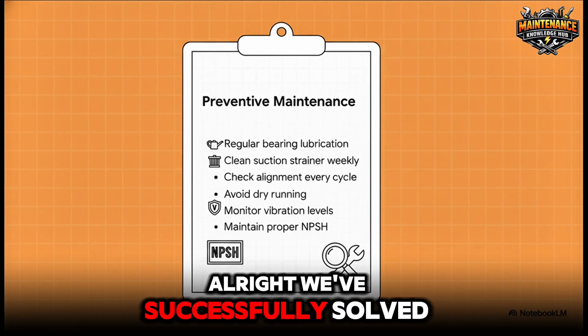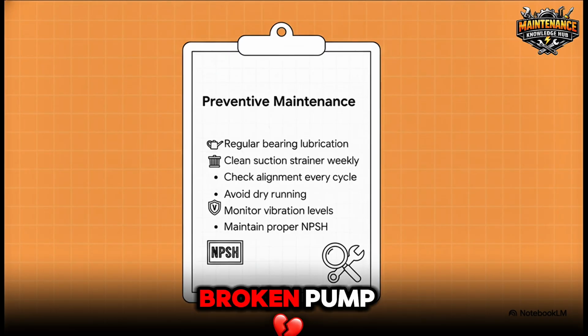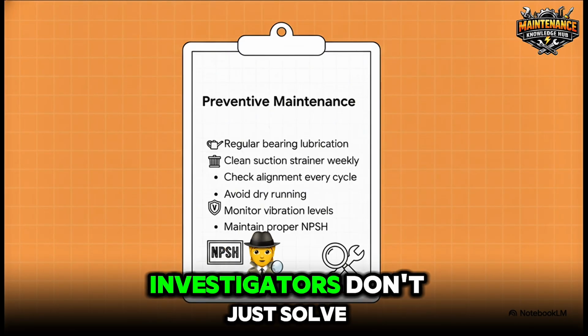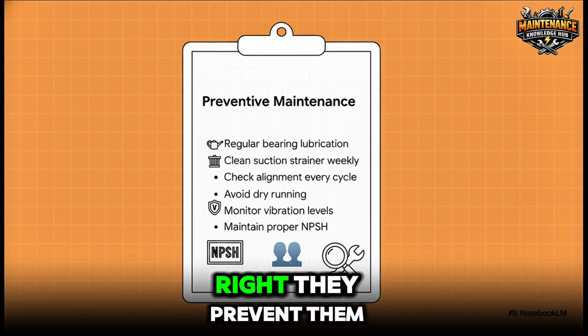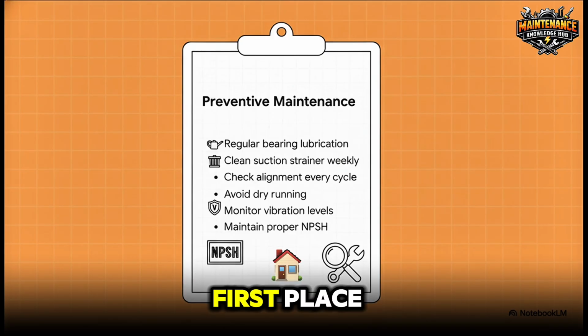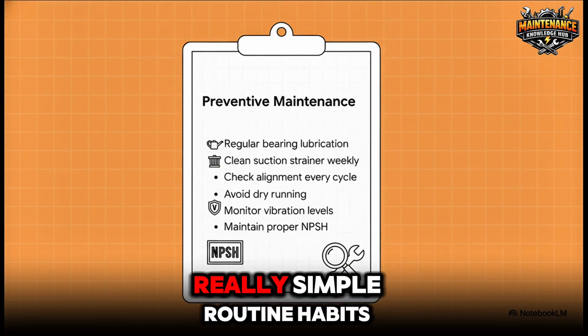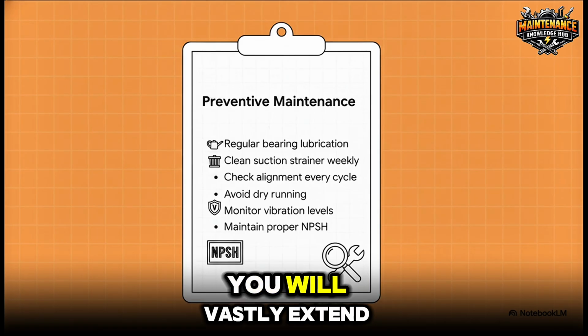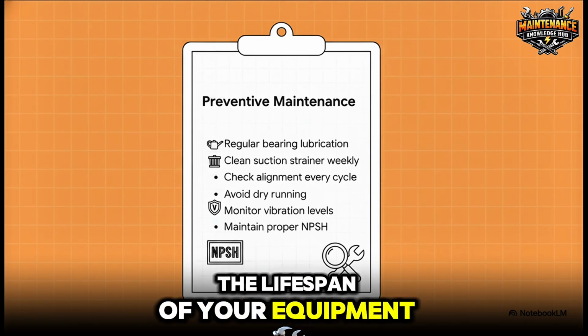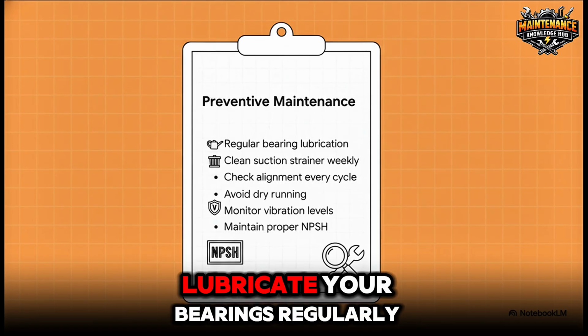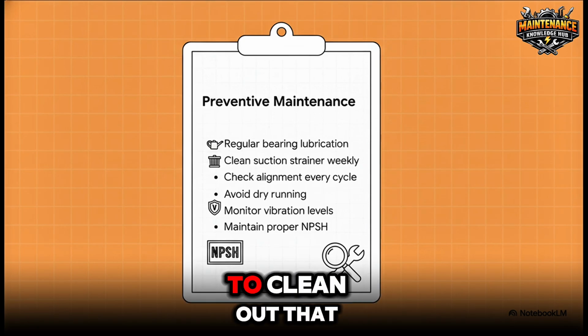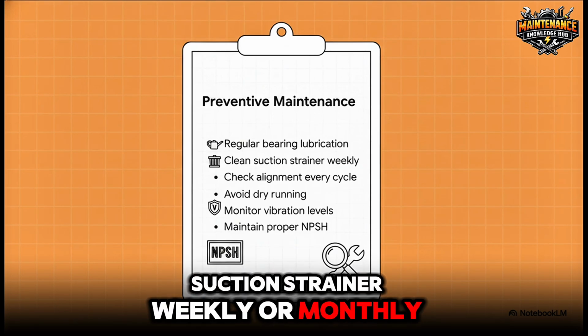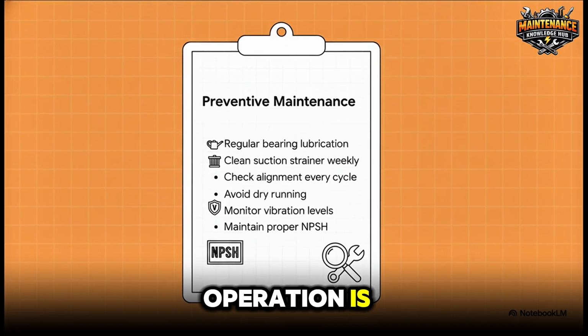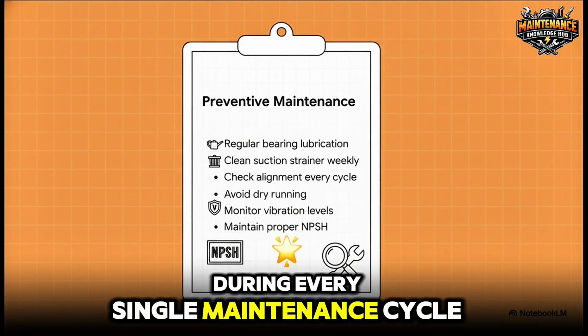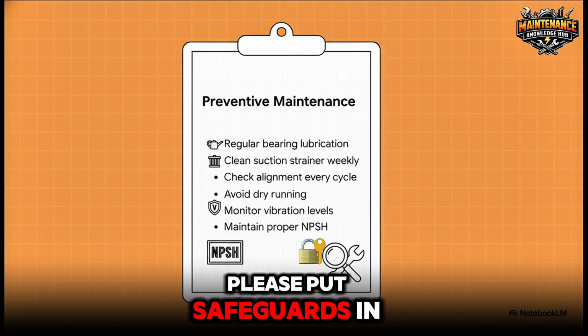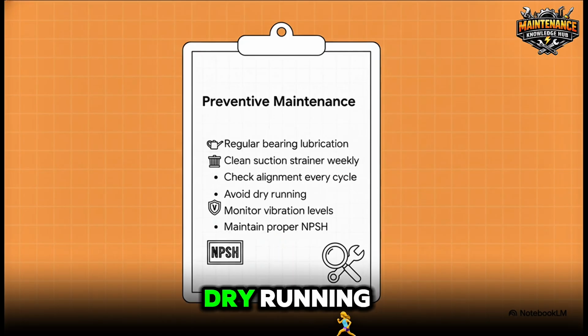All right, we've successfully solved the mystery of the broken pump. But hey, the best investigators don't just solve crimes after the fact, right? They prevent them from happening in the first place. By establishing a few really simple routine habits, you will vastly extend the lifespan of your equipment. First, make sure you lubricate your bearings regularly. Get on a schedule to clean out that suction strainer weekly or monthly, depending on how heavy your operation is. Check your coupling alignment during every single maintenance cycle. Please, put safeguards in place to absolutely avoid any dry running.